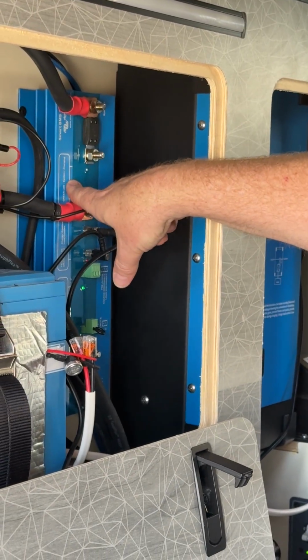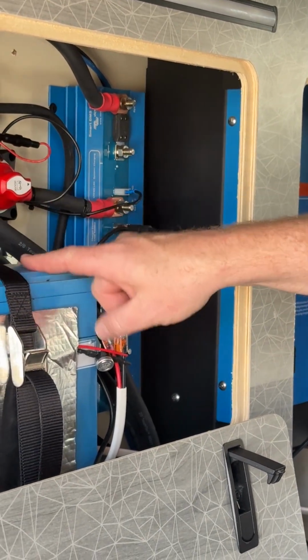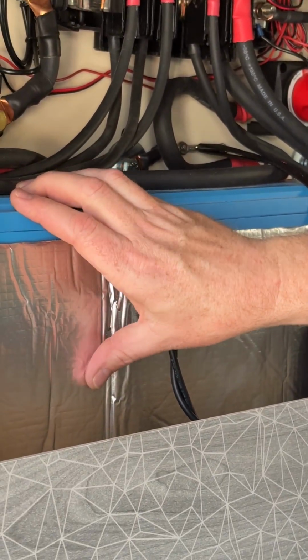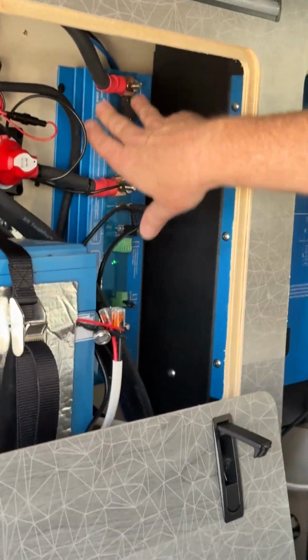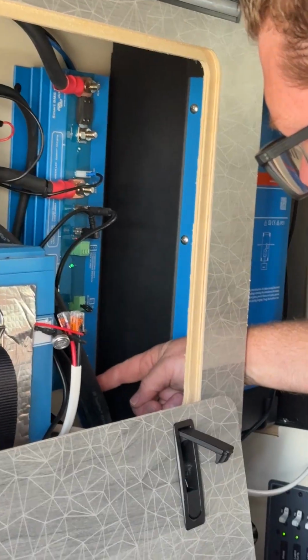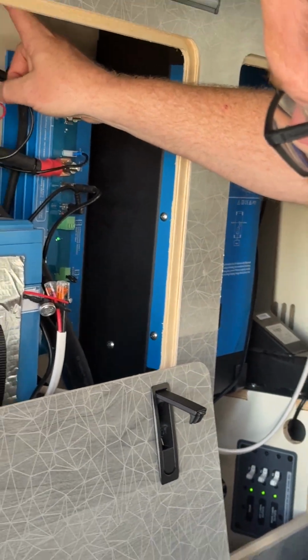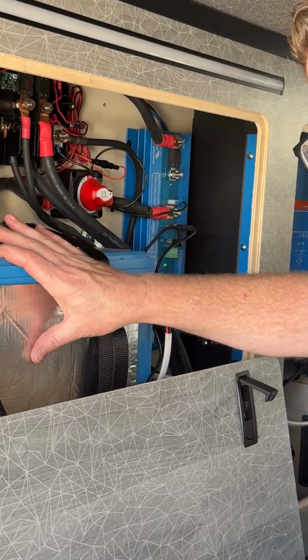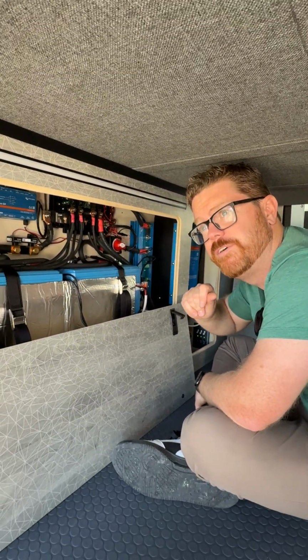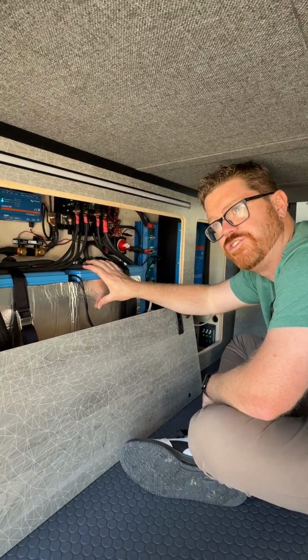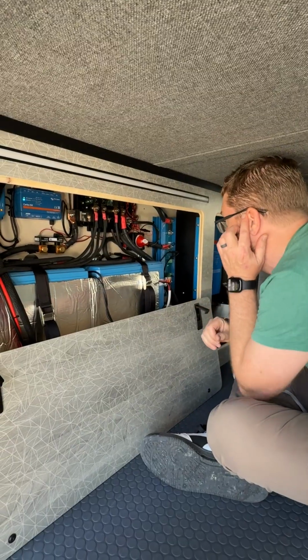Then they flow through this here, the BMS 12200. That's our battery management system that balances the loads on the batteries. These black wires go to the internal battery cells and do load balancing, so this maintains all of that. It also regulates power coming in from the vehicle through the Orion, and regulates power going out to the system. If it senses the batteries are too low or something like that, it'll shut everything off, keeping the batteries from over discharging. So it keeps the batteries safe.